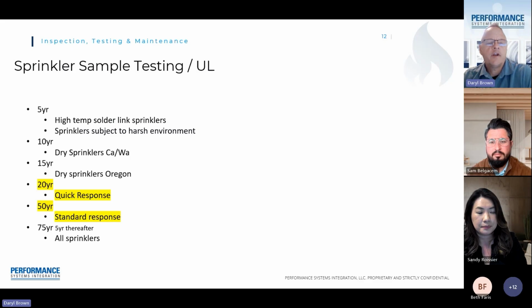Some of the over and above requirements for fire sprinkler heads have to do with 20-year and 50-year testing. Basically, the sprinkler head, like we said, is set to activate at a certain temperature rating. So every 20 or 50 years, we actually have to take samples of these sprinkler heads and send them to Underwriters Laboratory, and they test them for response to verify they do activate according to the temperature rating.